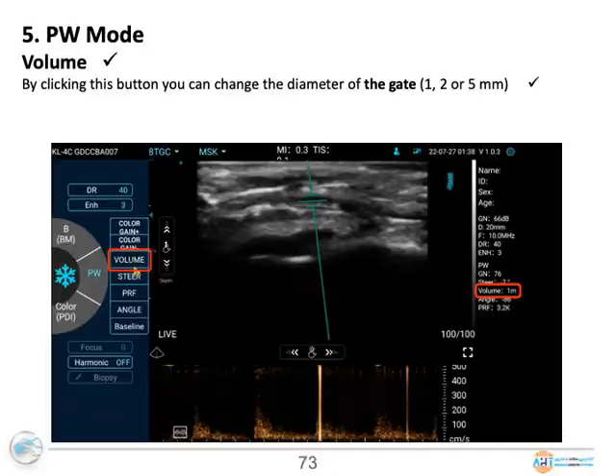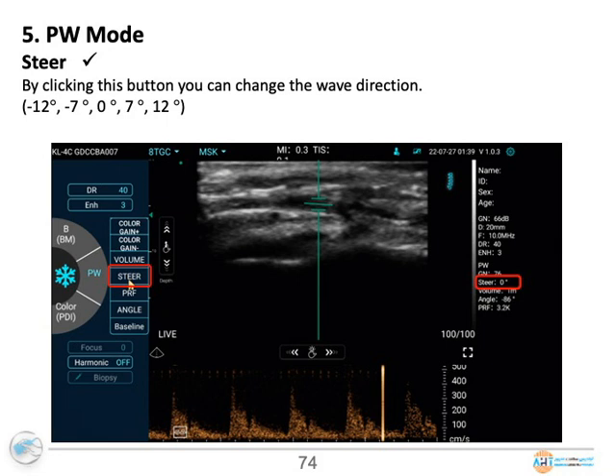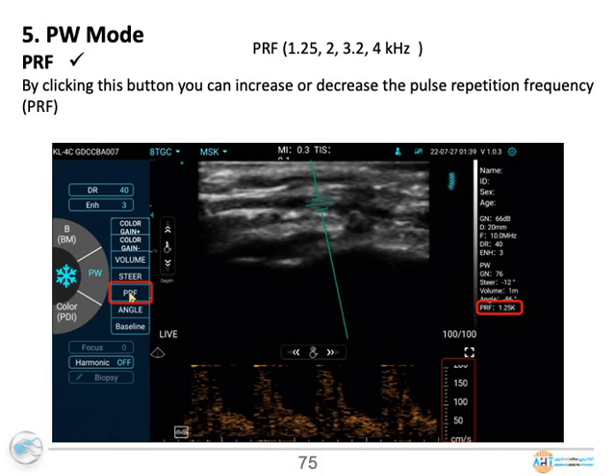PW mode. Volume. By clicking this button, you can change the diameter of the gate. 1, 2, or 5 millimeters. PW mode. Steer. By clicking this button, you can change the wave direction. Minus 12 degrees, minus 7 degrees, 0, 7 degrees, and 12 degrees. PW mode. PRF. By clicking this button, you can increase or decrease the pulse repetition frequency, PRF.